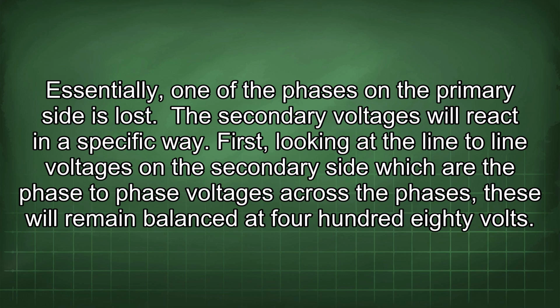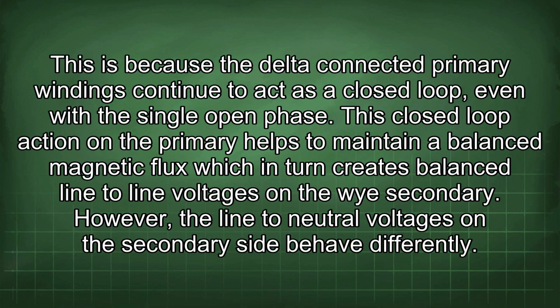First, looking at the line-to-line voltages on the secondary side, which are the phase-to-phase voltages across the phases, these will remain balanced at 480 volts. This is because the delta-connected primary windings continue to act as a closed loop even with a single open phase. This closed-loop action on the primary helps to maintain a balanced magnetic flux, which in turn creates balanced line-to-line voltages on the Y secondary. However, the line-to-neutral voltages on the secondary side behave differently.